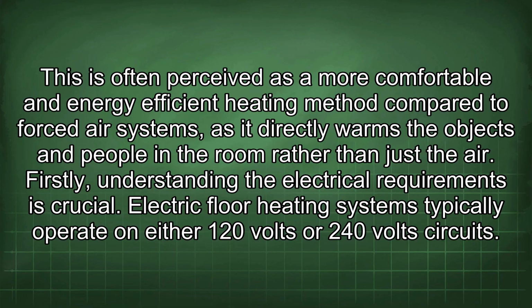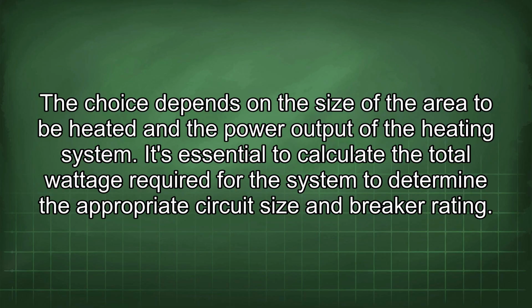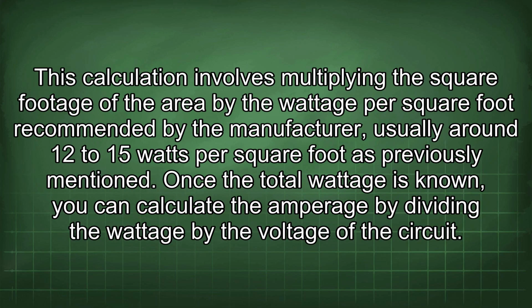Firstly, understanding the electrical requirements is crucial. Electric floor heating systems typically operate on either 120 volt or 240 volt circuits. The choice depends on the size of the area to be heated and the power output of the heating system. It's essential to calculate the total wattage required for the system to determine the appropriate circuit size and breaker rating. This calculation involves multiplying the square footage of the area by the wattage per square foot recommended by the manufacturer, usually around 12 to 15 watts per square foot as previously mentioned.